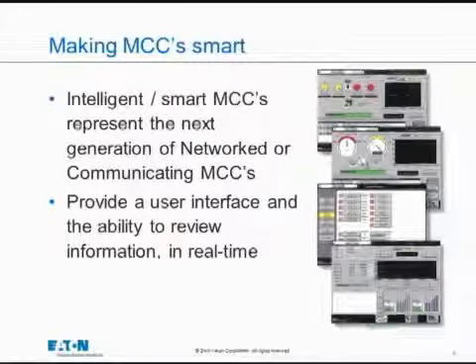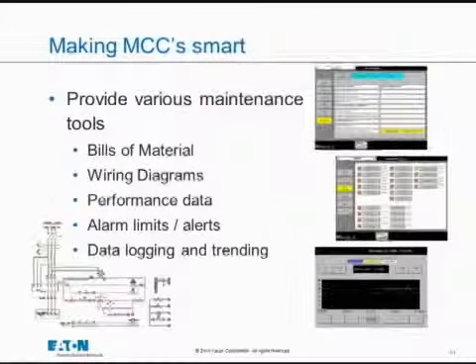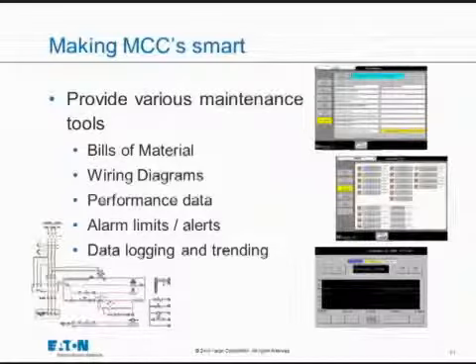Typically, smart MCCs have what I call a default or a summary page, which will always show you. And that summary page will always give you information at a glance to show you what the status is. It's a graphical representation, typically, of the motor control center itself, showing where each bucket or wrapper is located and the orientation of those wrappers and the state that it's in. And you're going to find typical information there that's alarms, alerts, load status, and general operating data.